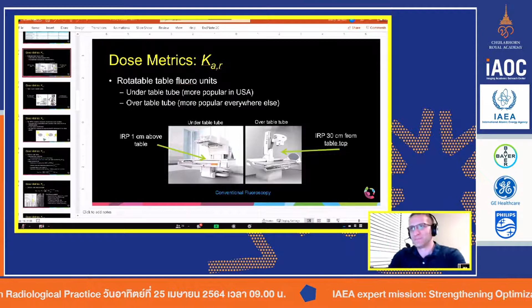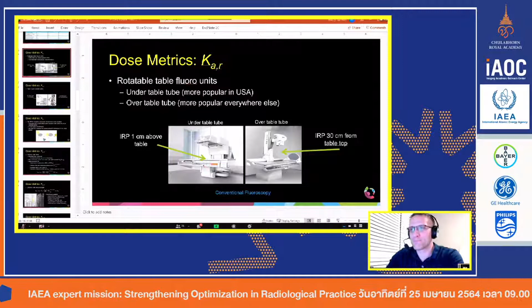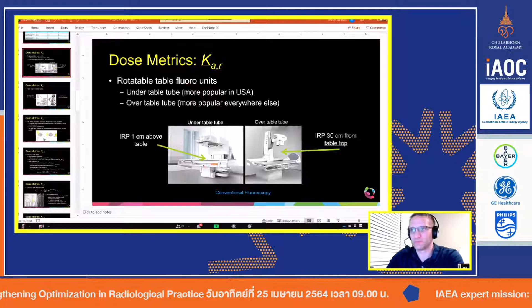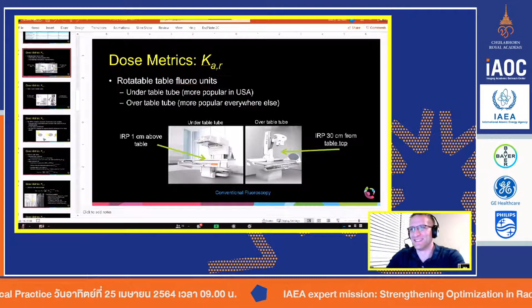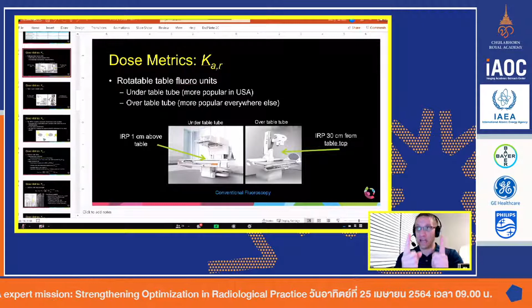That makes sense. Yeah. Next question is about the 3 options you gave us on the measurement, right? For the third option, using the air method, can we use the 100 millimeter ion chamber for this test? Would you prefer to test on the detector or tube side? Sure. So let me answer that. The answer is, if you do choose to use the 100 millimeter chamber in air, that's fine, as long as your field of view is less than 100 millimeters.